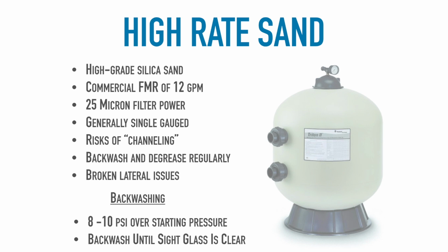Well, we backwash simply until the sight glass is clear. There is a sight glass that will be installed on your system, and if you don't have one installed on your system, make sure that you get one installed, because they are required by code and they are extremely helpful, especially because we no longer have to go off of "we backwash here every 3 days and we do it for 5 minutes" sort of mentality.